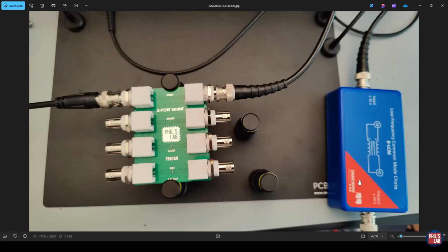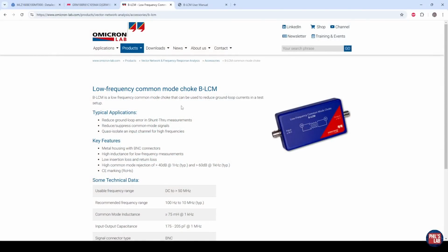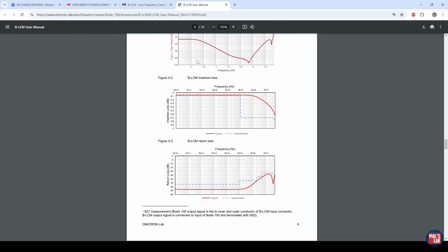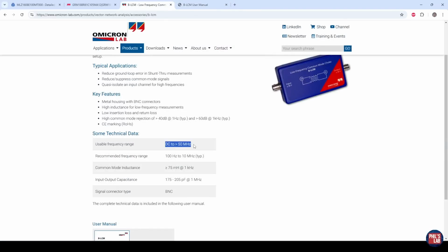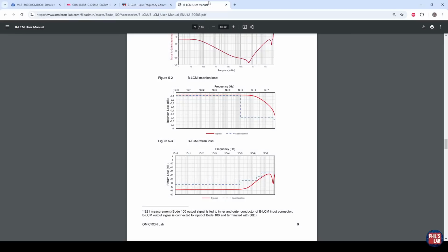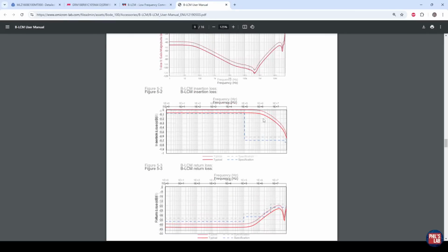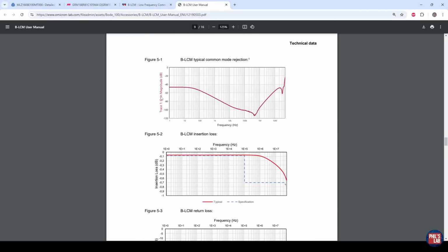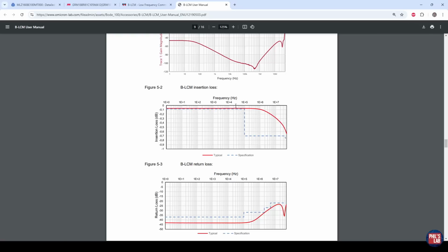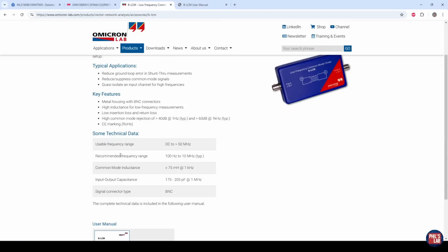Now, what we have to keep in mind with the calibration and with the measurements is that this low frequency common mode choke has a somewhat limited recommended frequency range. Looking at the webpage for this BLCM as well as the datasheet, we can see that the usable frequency range they say is DC to above 50 MHz, but recommended is 100 Hz to 10 MHz. And going into the actual datasheet, we can see insertion losses, return losses, and typical common mode rejection ratios versus frequency. So that's something to keep in mind, what frequency range you calibrate to. I'd suggest if you use this part, following the recommended frequency range, that is 100 Hz to 10 MHz.